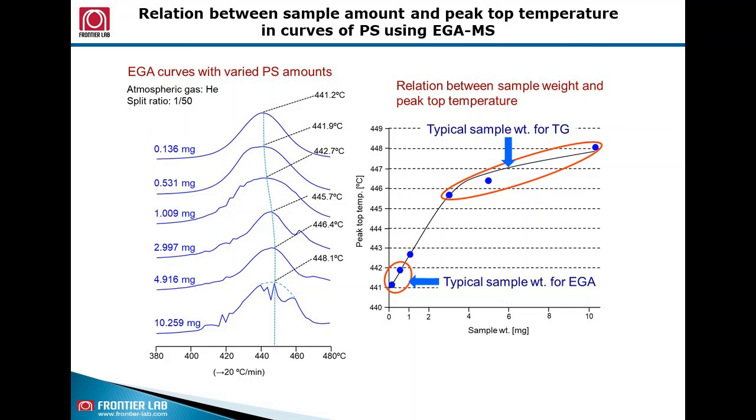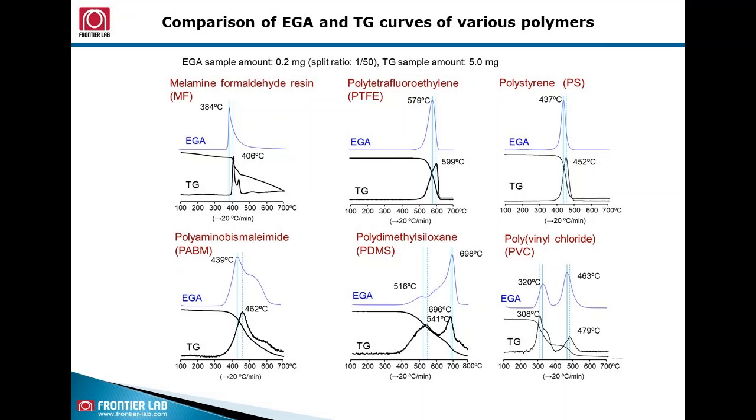To demonstrate the sample mass effect, we have investigated different masses of sample. From the results, it is evident there is a shift in apex temperature when sample mass is higher. We have obtained temperature profiles of 10 different polymers with both instruments.